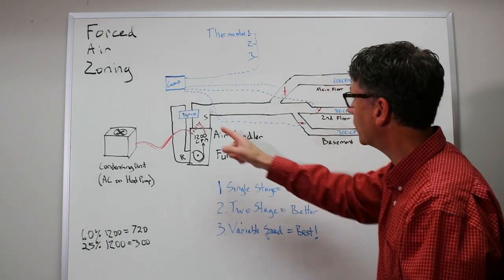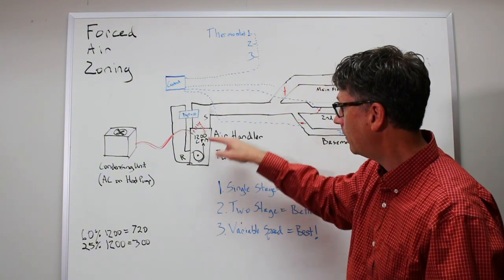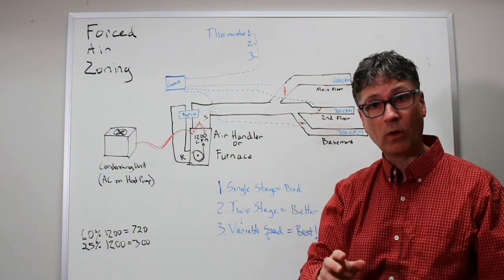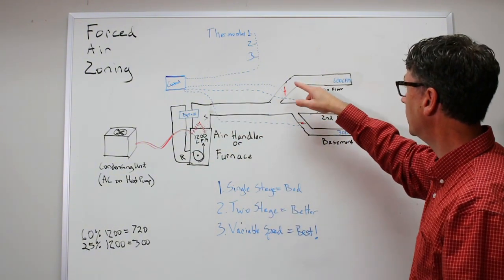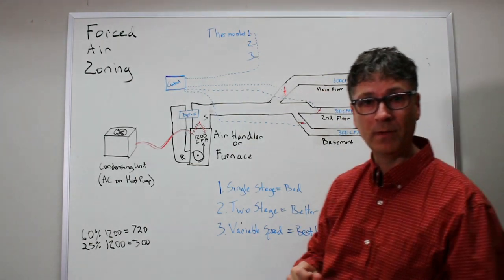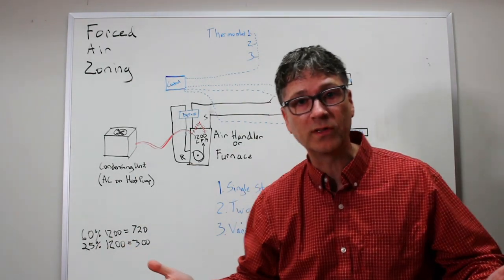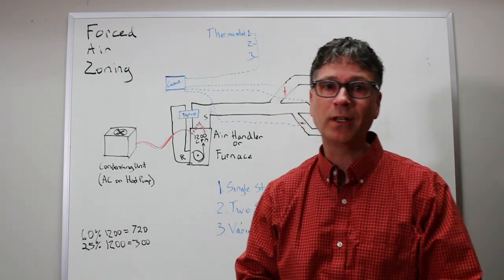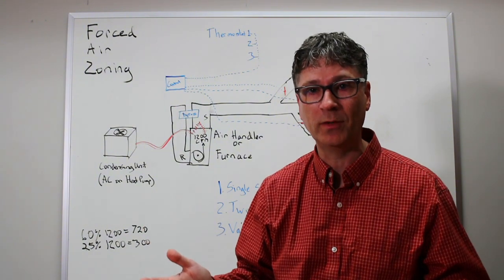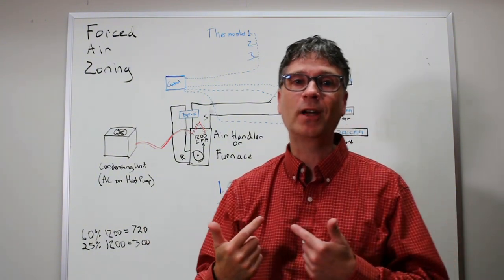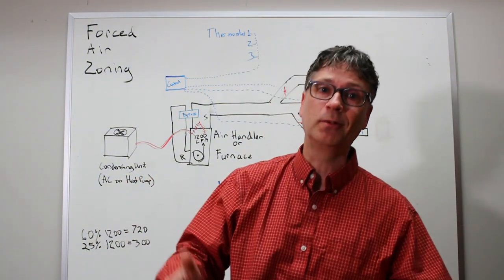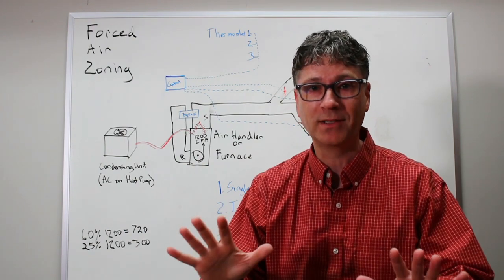And now it circulates across the bypass here and may overcool this coil, or the zone controller may decide to open another zone and dump out some extra cooling, which overcools that zone. Forced air zoning in this situation is really pretty primitive. If an HVAC contractor sold you one of these systems, let's say 20 years ago, you have my sympathies.